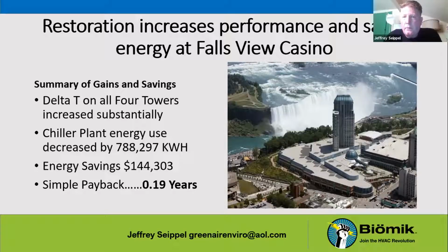This was a project that we did at the Niagara Falls Casino in New York. We had a third-party engineer do the study, and what they found was that in all four of the towers that we worked on, we increased the delta T, which means the difference in temperature of the water. So that's a performance metric.